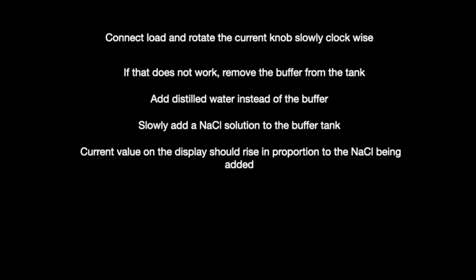If you do not get expected results, remove the buffer from the tank. Add distilled water instead of the buffer and then slowly add a NaCl solution to the buffer tank. The current value on the display should rise in proportion to the NaCl being added. If this is not the case, contact us at sales@technosource.in. This concludes the section on what to do if current values stay at 0.